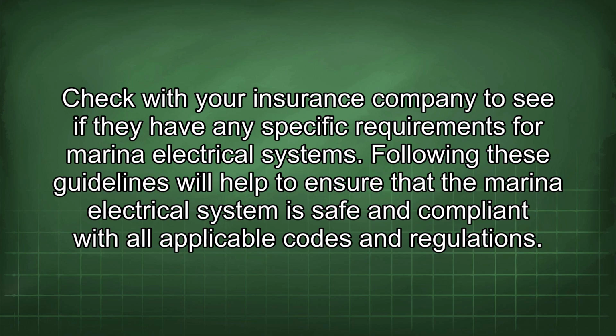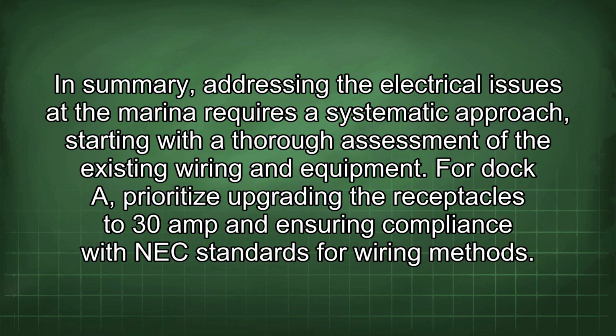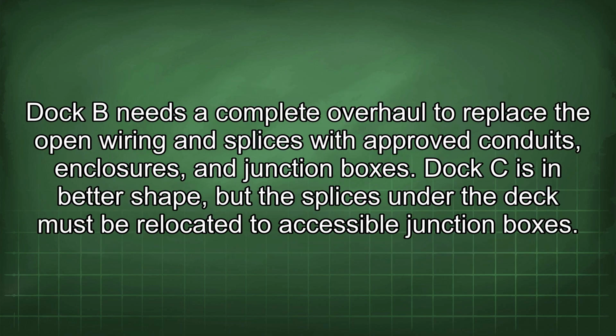Following these guidelines will help to ensure that the marina electrical system is safe and compliant with all applicable codes and regulations. In summary, addressing the electrical issues at the marina requires a systematic approach, starting with a thorough assessment of the existing wiring and equipment. For Dock A, prioritize upgrading the receptacles to 30 amp and ensuring compliance with NEC standards for wiring methods. Dock B needs a complete overhaul to replace the open wiring and splices with approved conduits, enclosures, and junction boxes. Dock C is in better shape, but the splices under the deck must be relocated to accessible junction boxes.